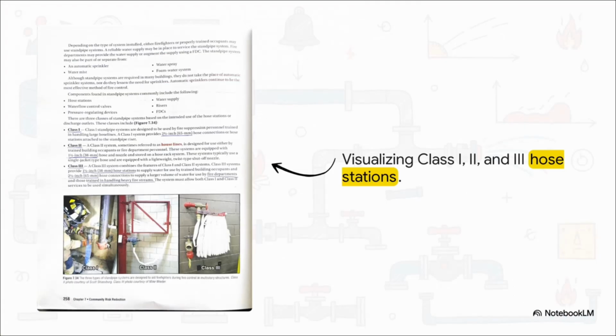And here is what those classes actually look like out in the wild. If you look closely, the Class 1 station is just a heavy-duty, bare metal connection valve just sitting there waiting for a firefighter to hook up a hose. With Class 2, you can see the lightweight single jacket hose pre-connected and neatly folded right there on a rack, completely ready for a trained occupant to grab in an emergency. And a Class 3 setup gives you both of those options sitting right side by side.